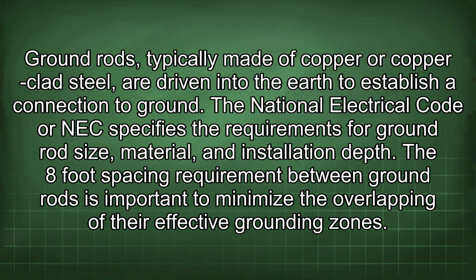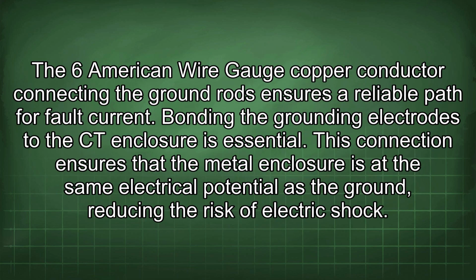Ground rods, typically made of copper or copper-clad steel, are driven into the earth to establish a connection to ground. The National Electrical Code or NEC specifies the requirements for ground rod size, material, and installation depth. The 8-foot spacing requirement between ground rods is important to minimize the overlapping of their effective grounding zones. The 6 American wire gauge copper conductor connecting the ground rods ensures a reliable path for fault current.